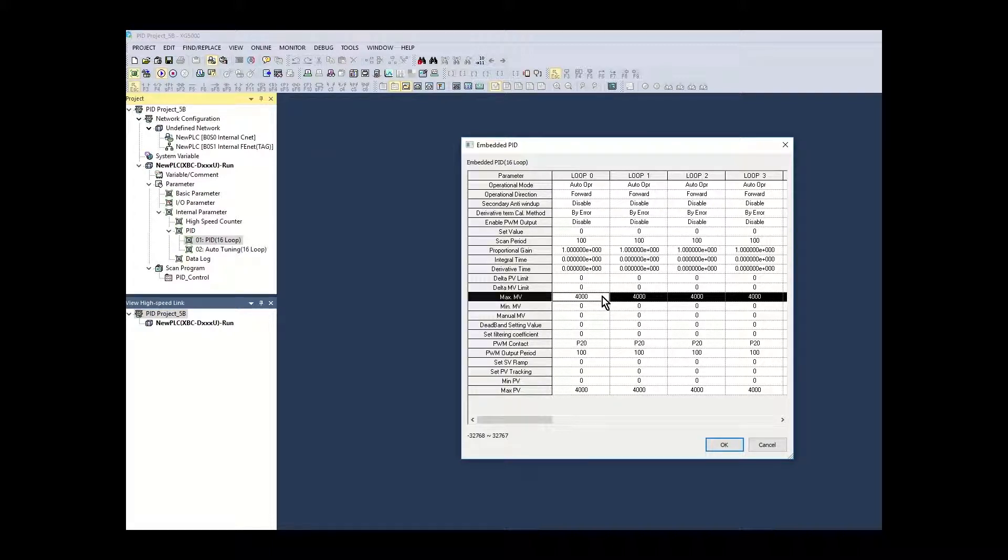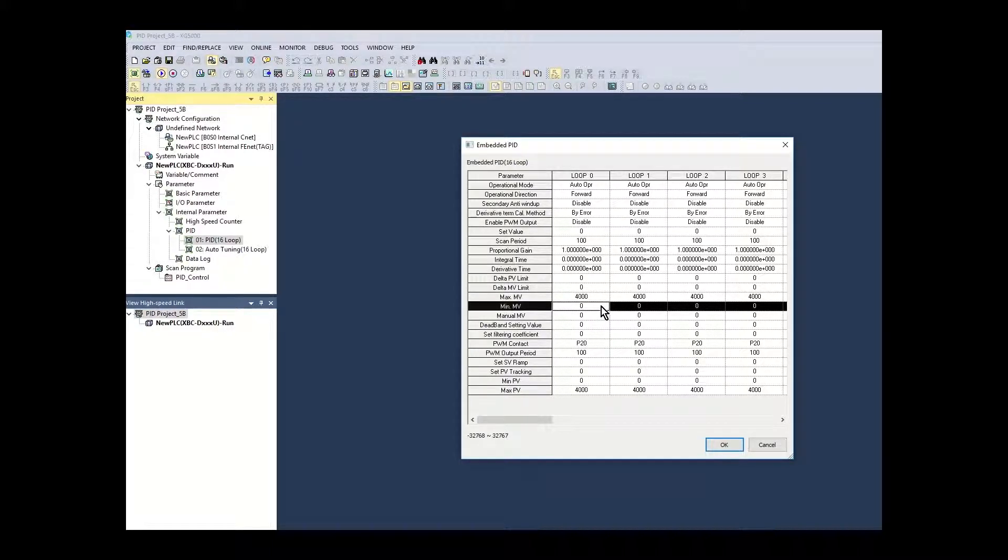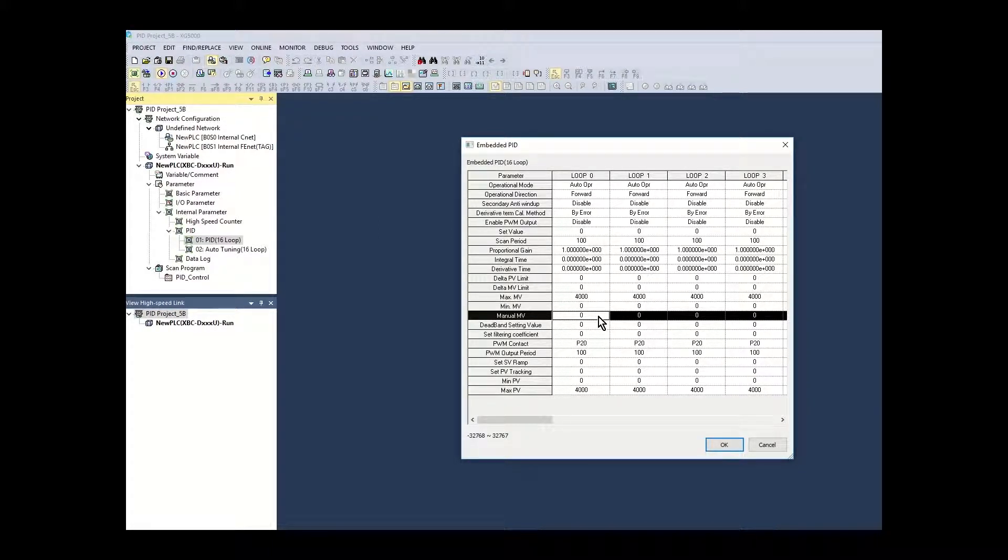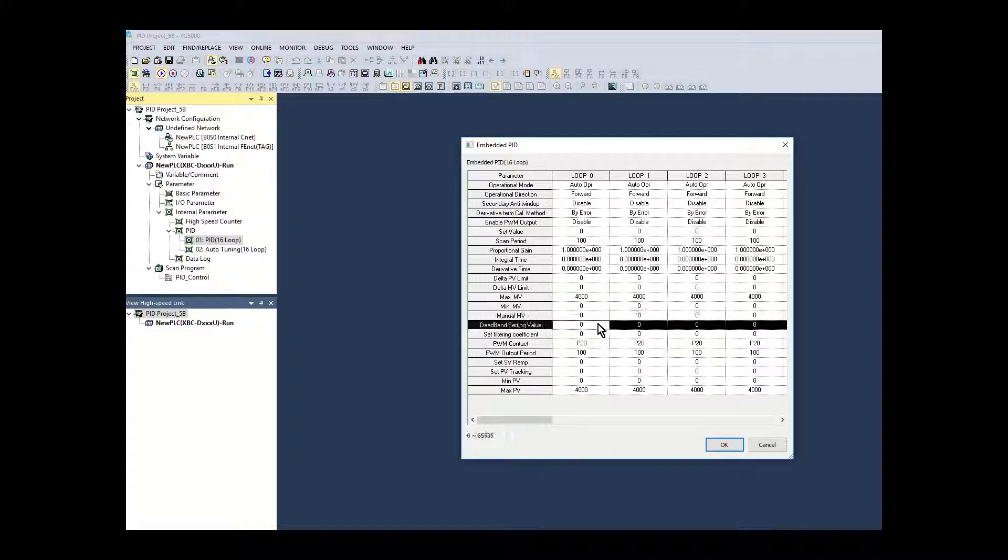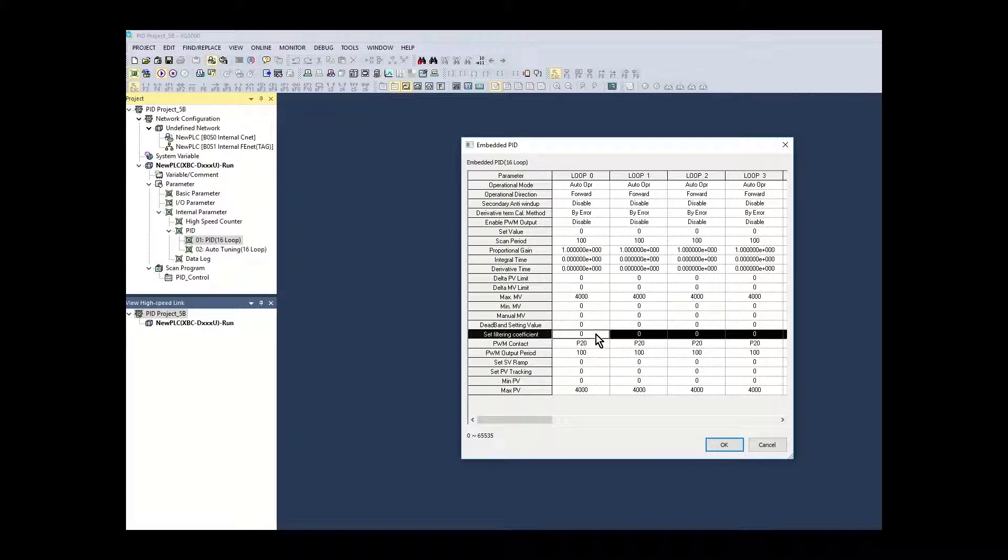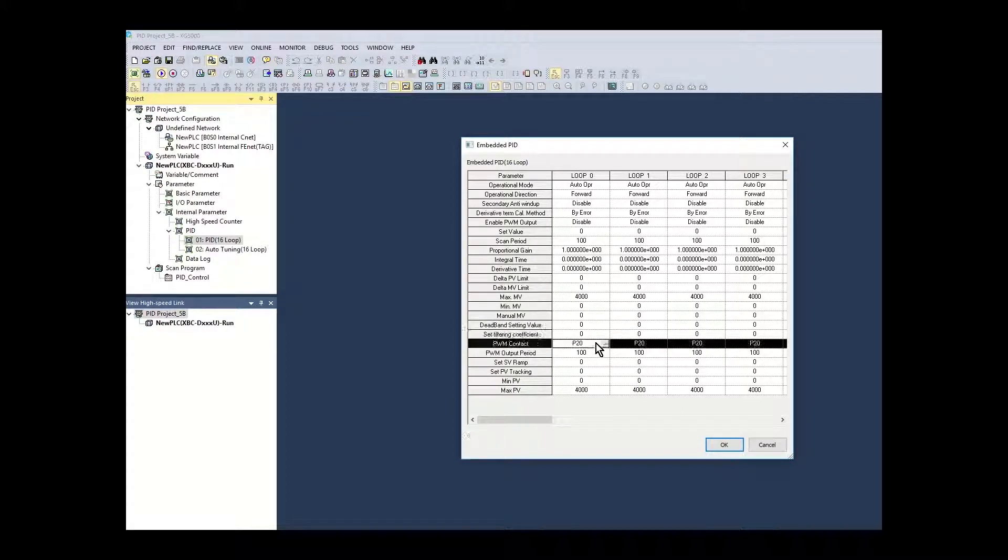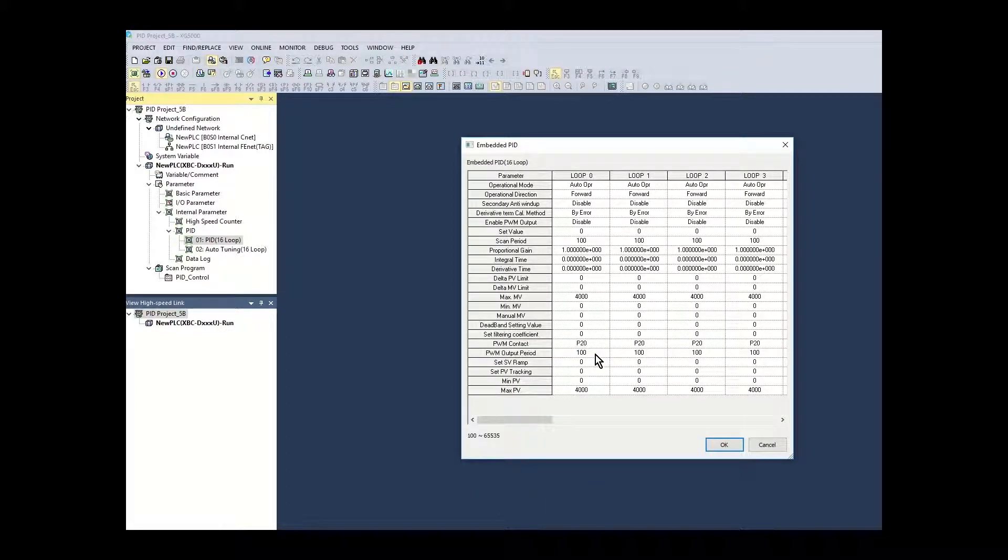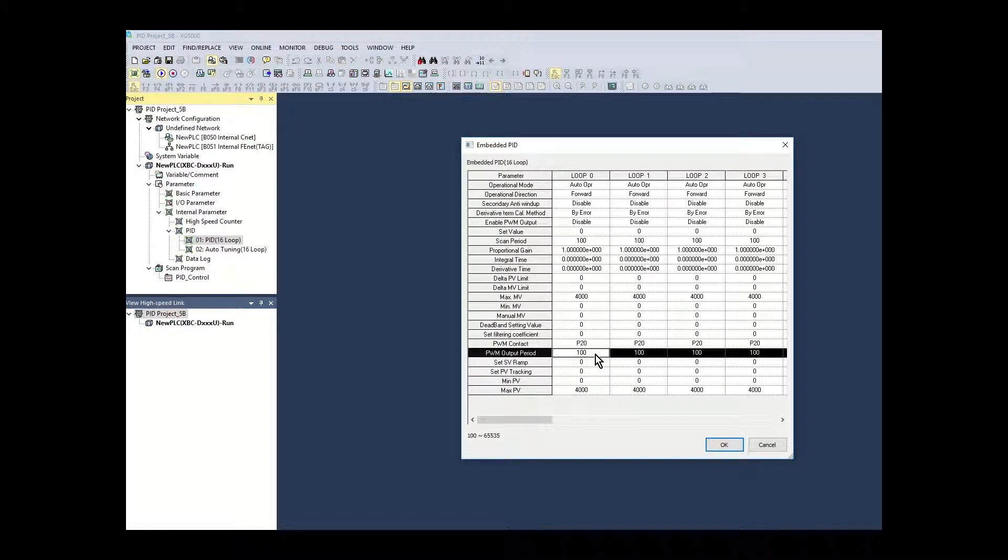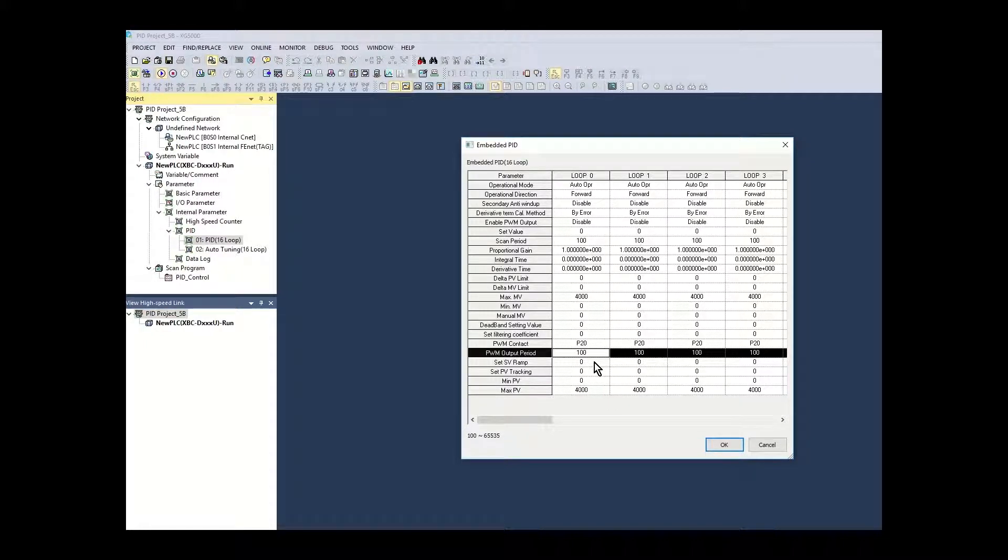The MV max and min values set the range the MV can output. They are left at the total range of the PID control loop. The manual MV is left at zero. The dead band setting value is left at zero. The set filtering coefficient is left at zero. The PWM contact is left at default as PWM MV output has been disabled. The PWM output period is left at default. It is not used in the PID loop in this application.